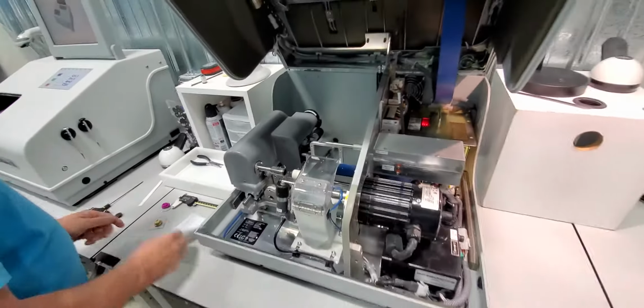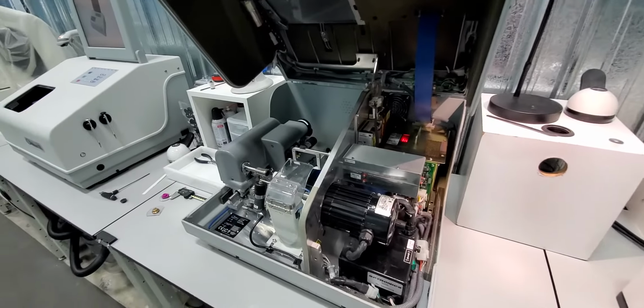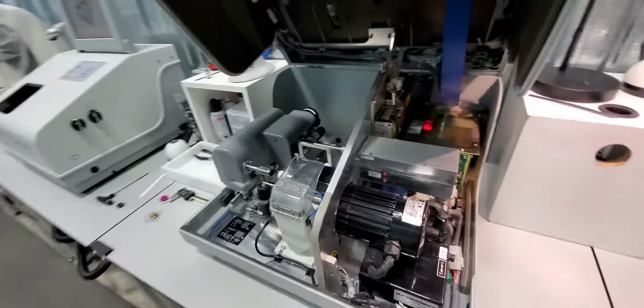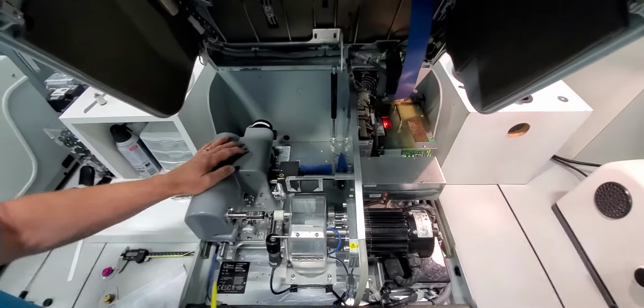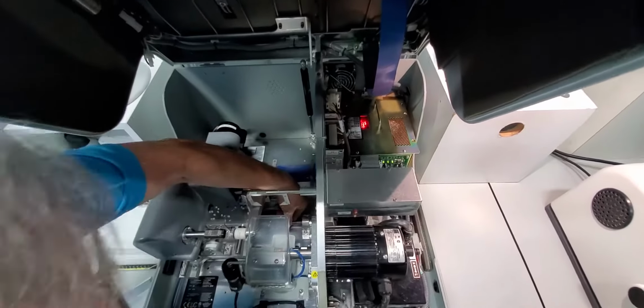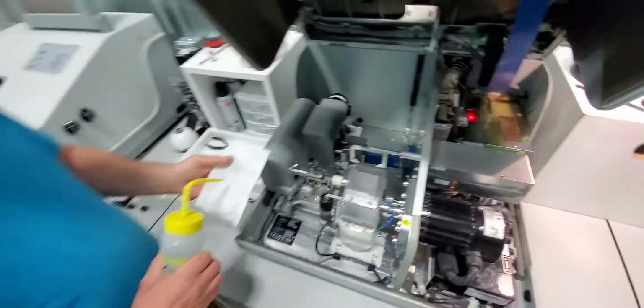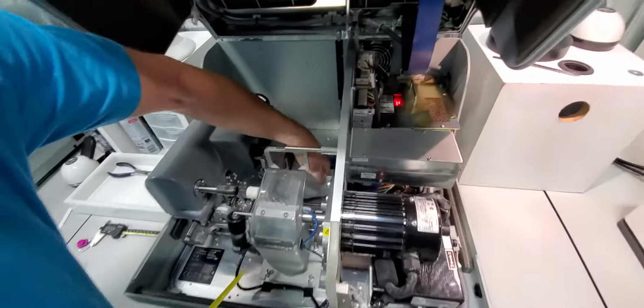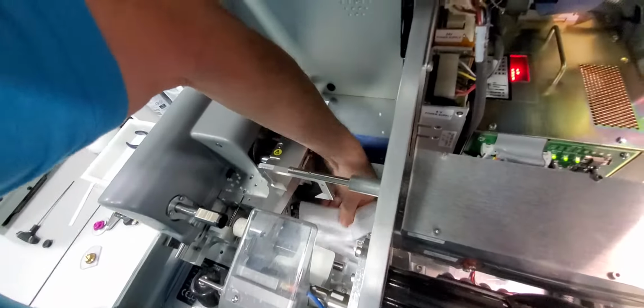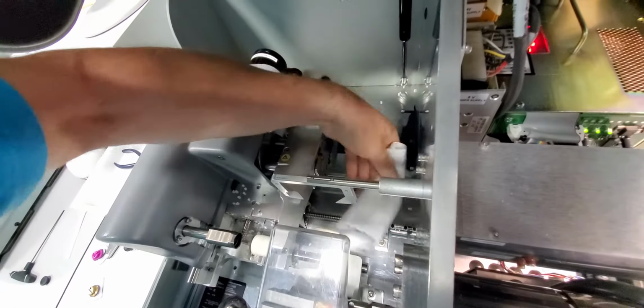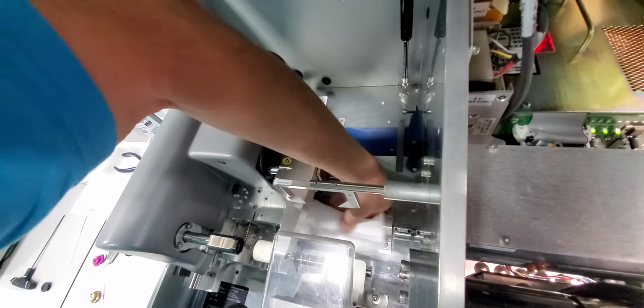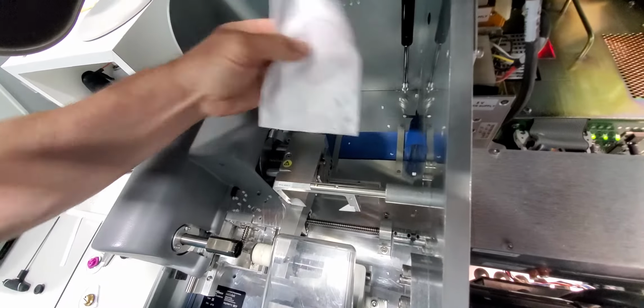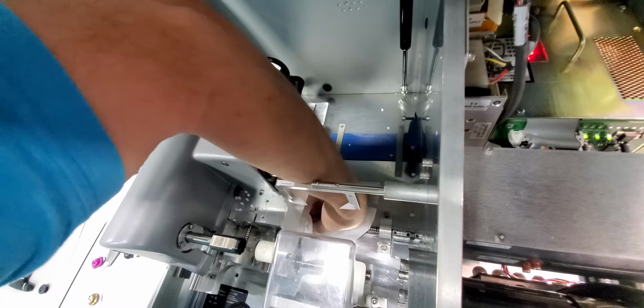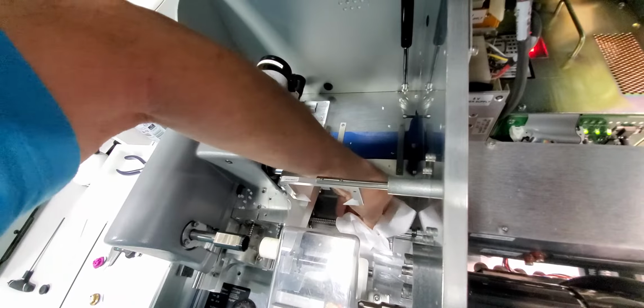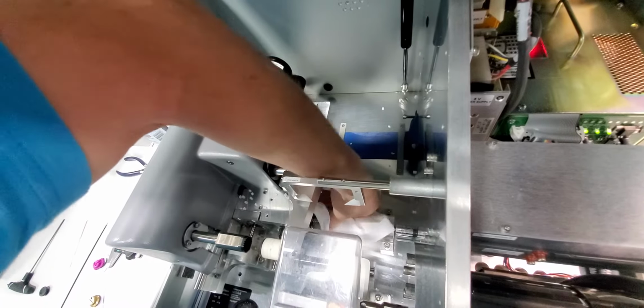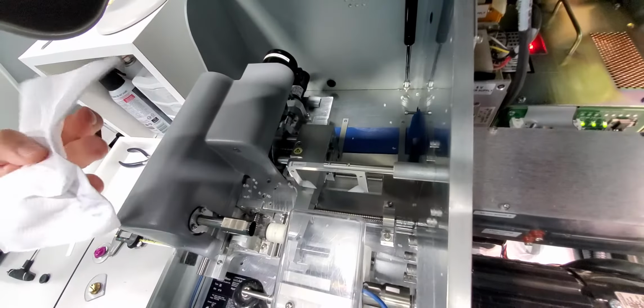Perfect. Thanks, Mike. Next we can move on to cleaning the lead screws. So your lead screws are right here. Take some alcohol, put it on there, go right on the screw itself. If it's very dirty, you'll get a lot of grime off of it here. But you want to do it weekly, no matter how much you get off of there. Want it to be nice and squeaky clean.